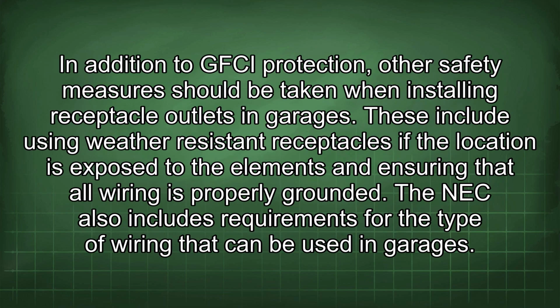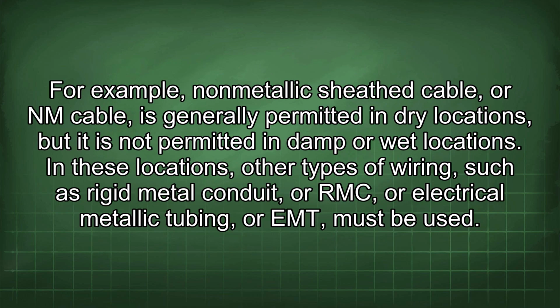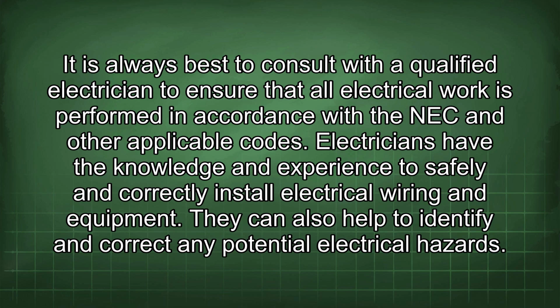In addition to GFCI protection, other safety measures should be taken when installing receptacle outlets in garages. These include using weather-resistant receptacles if the location is exposed to the elements and ensuring that all wiring is properly grounded. The NEC also includes requirements for the type of wiring that can be used in garages. For example, non-metallic sheathed cable, or NM cable, is generally permitted in dry locations, but it is not permitted in damp or wet locations. In these locations, other types of wiring, such as rigid metal conduit, or RMC, or electrical metallic tubing, or EMT, must be used.